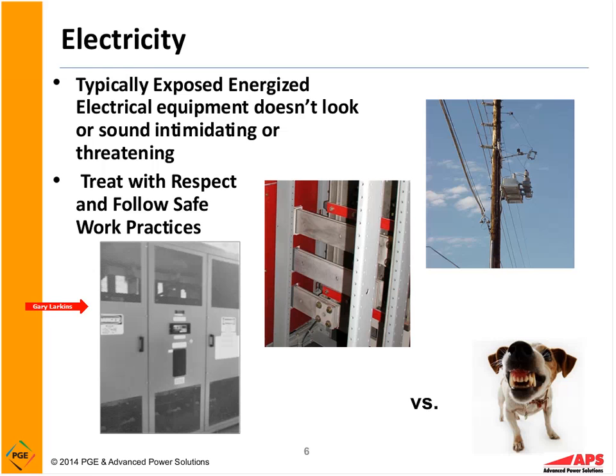So in the middle picture here, again, I open up that cabinet and that's 277 volts. You see the three bus bars there? That's a bus bar right there. Over here is a grounded surface, 277 volts on that bus bar to ground, 480 volts phase to phase. Now, if anything, you might just hear a little hum, but it doesn't sound intimidating.